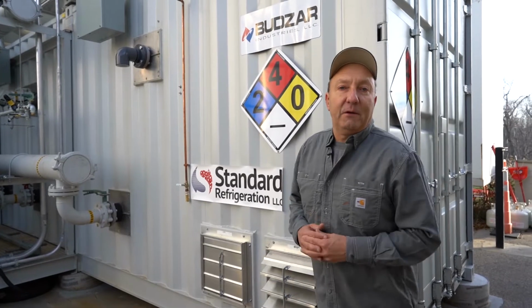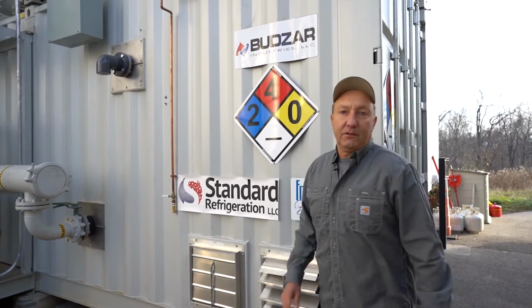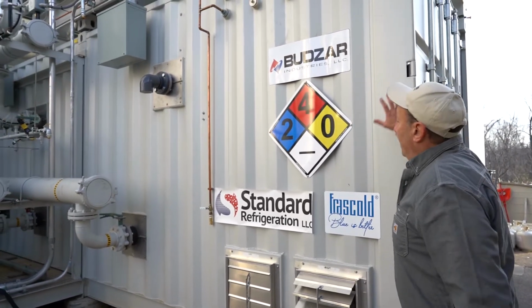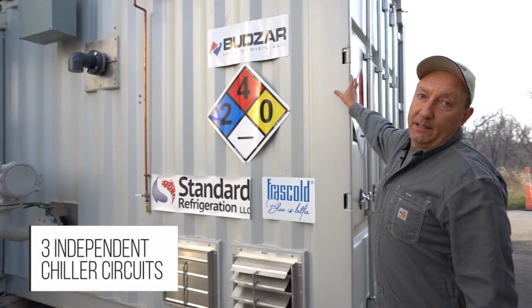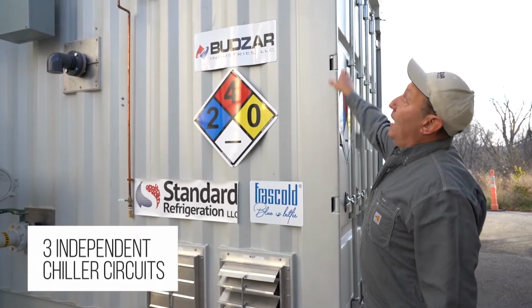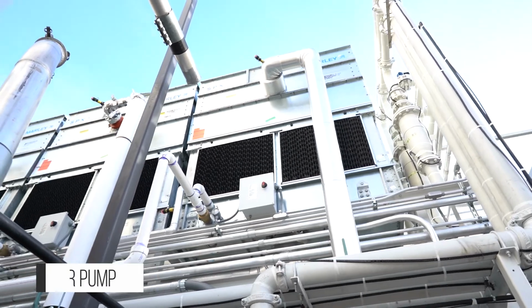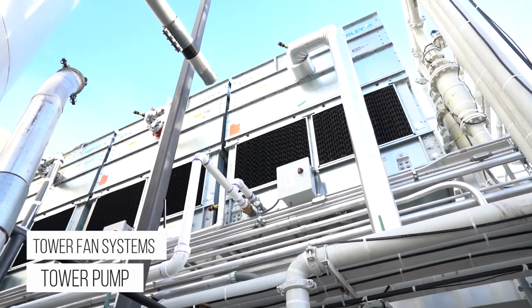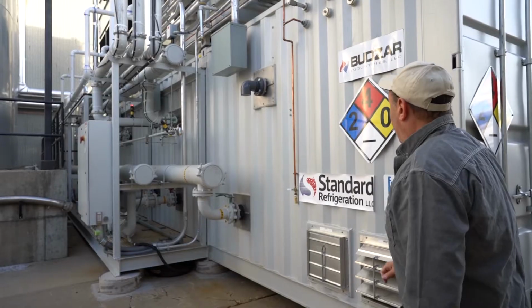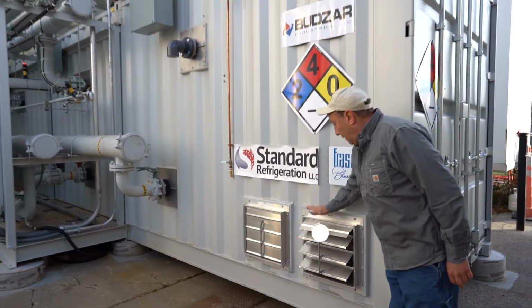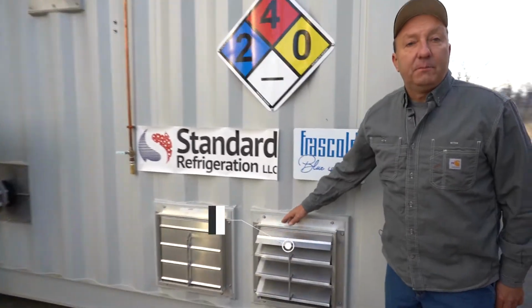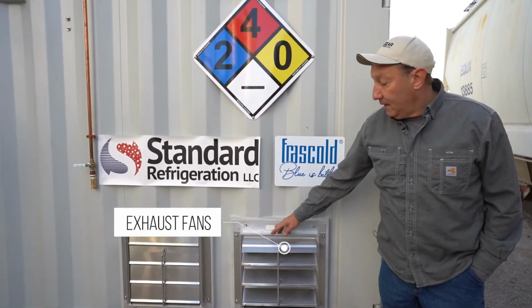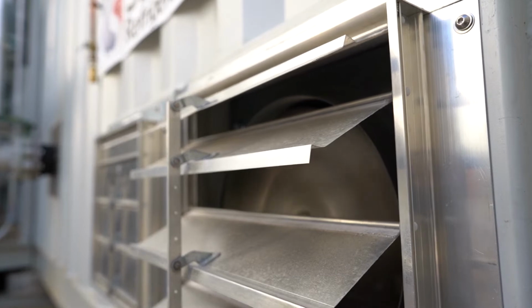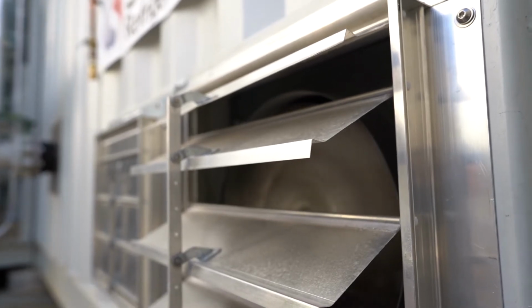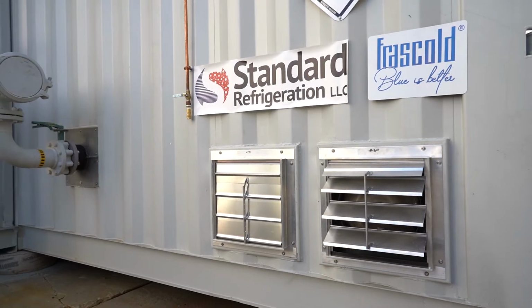Okay, here we are on the outside of our process container system. Inside the container we have 3 independent chiller circuits. On top, we have our tower pump system, our tower fan system, and our process pump systems. To quickly go through everything, these are our exhaust fans. Because of the R290 propane, the system constantly has airflow from one end to the other. It also could be used for heating and cooling.